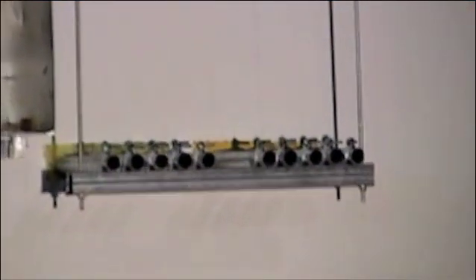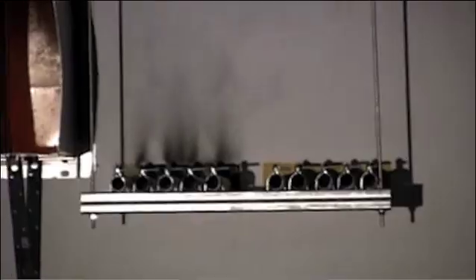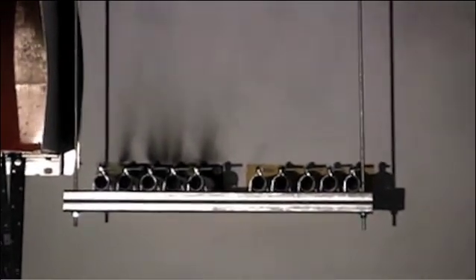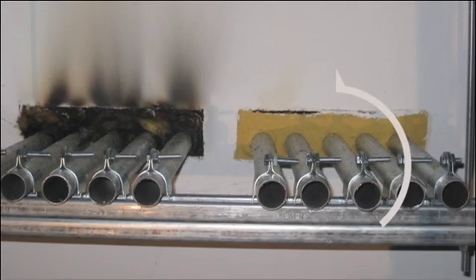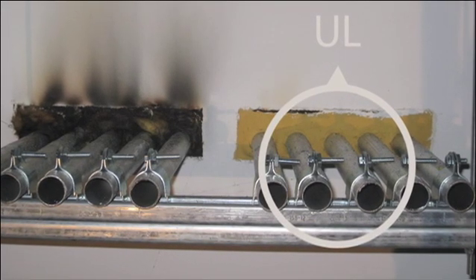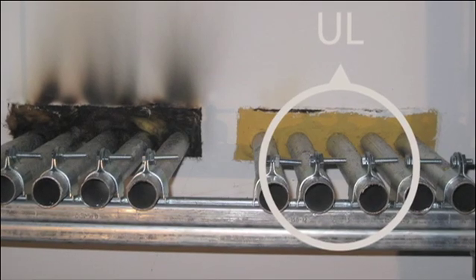Even materials with respectable fire properties will not hold up if used inappropriately. The hole for the five conduits on the left uses glass fiber insulation, a material that does well in non-combustibility, but in the event of a fire softens and yields considerably. Its lack of suitability for this installation allows smoke and hot gases to pass rapidly through the fiberglass stuffed openings.